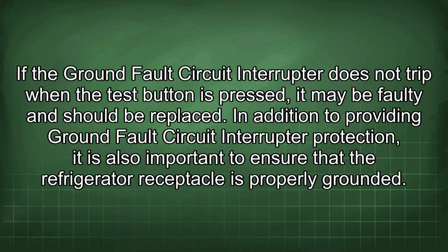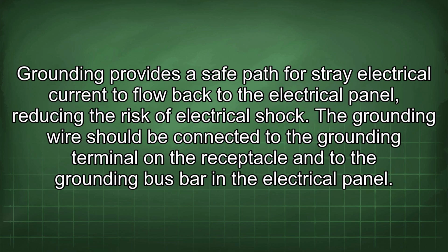If the ground fault circuit interrupter does not trip when the test button is pressed, it may be faulty and should be replaced. In addition to providing ground fault circuit interrupter protection, it is also important to ensure that the refrigerator receptacle is properly grounded. Grounding provides a safe path for stray electrical current to flow back to the electrical panel, reducing the risk of electrical shock. The grounding wire should be connected to the grounding terminal on the receptacle and to the grounding bus bar in the electrical panel.